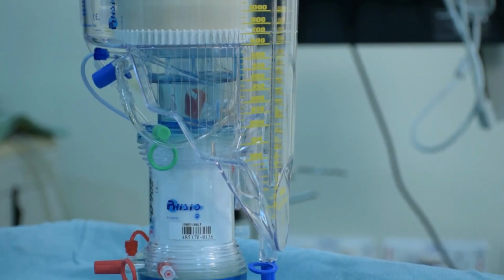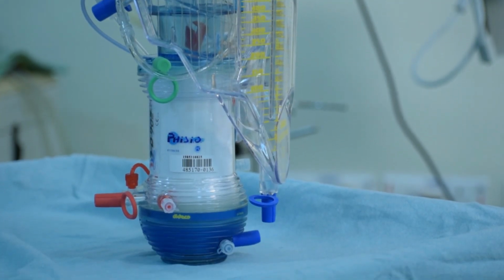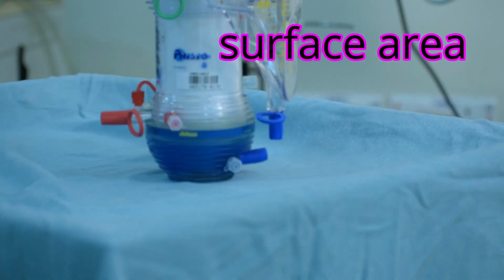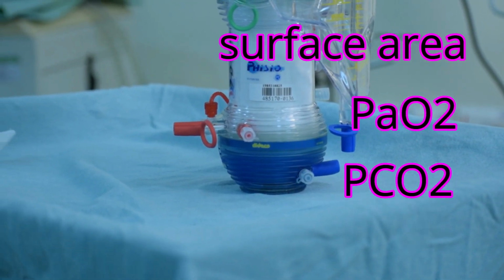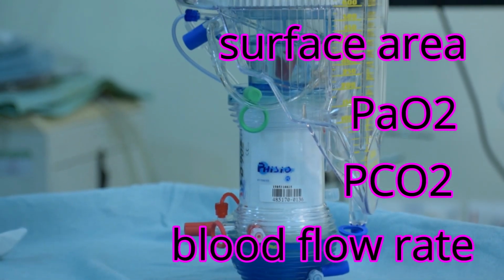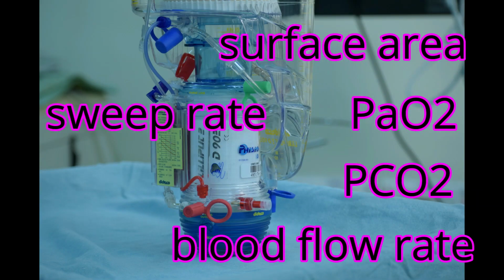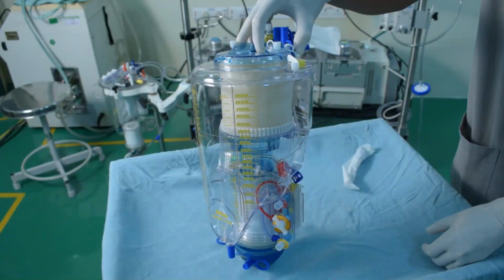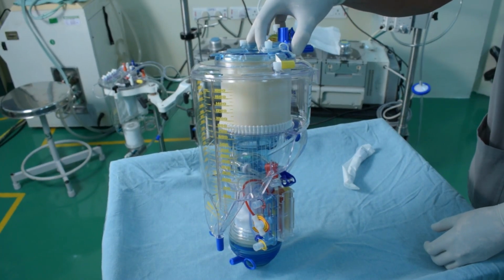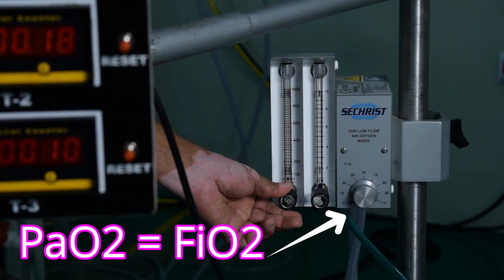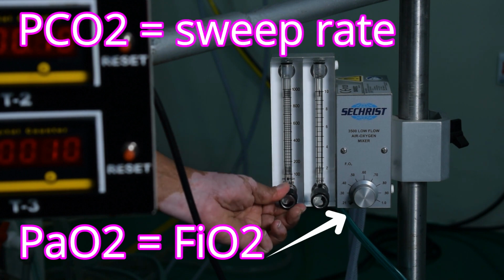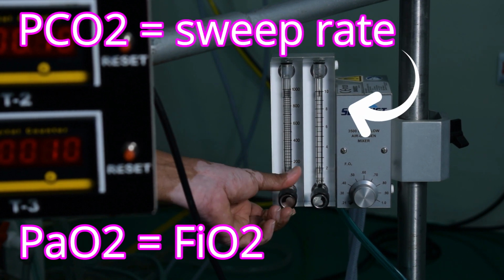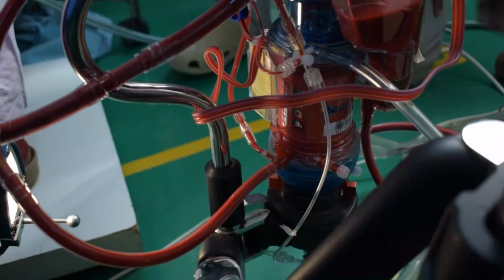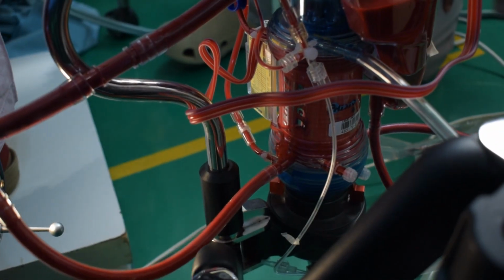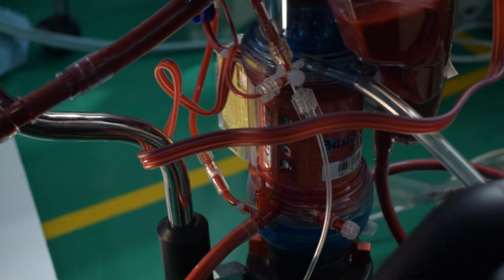Gas transfer in membranous oxygenators is a function of several factors that include surface area, the partial pressure of venous oxygen and carbon dioxide, the rate of blood flow, the ventilation flow, the so-called sweep rate, and gas flow composition. Partial pressure of oxygen is a function of FiO2, whereas the partial pressure of carbon dioxide is determined by the sweep rate of the ventilating gas.